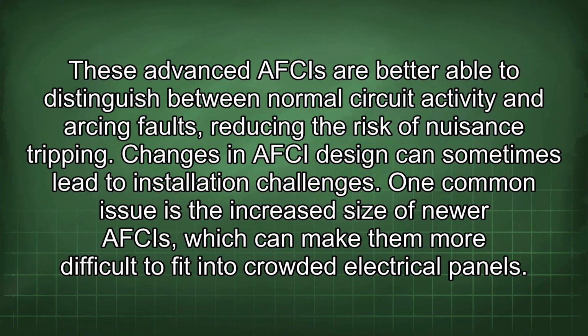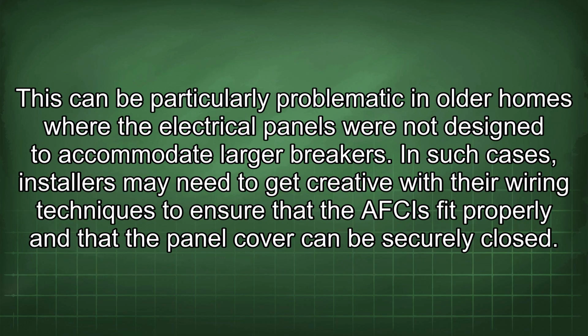One common issue is the increased size of newer AFCIs, which can make them more difficult to fit into crowded electrical panels. This can be particularly problematic in older homes where the electrical panels were not designed to accommodate larger breakers. In such cases, installers may need to get creative with their wiring techniques to ensure that the AFCIs fit properly and that the panel cover can be securely closed.